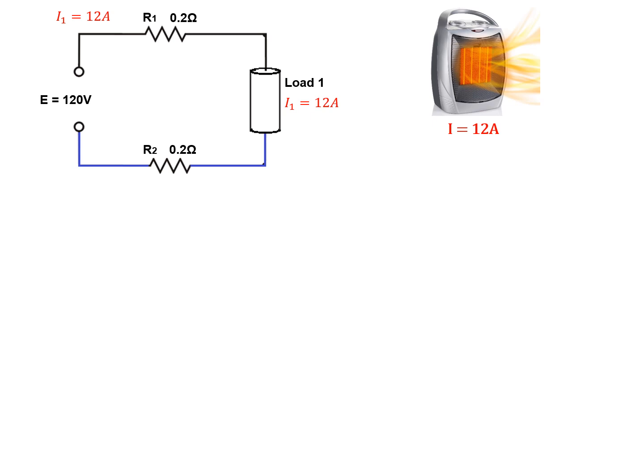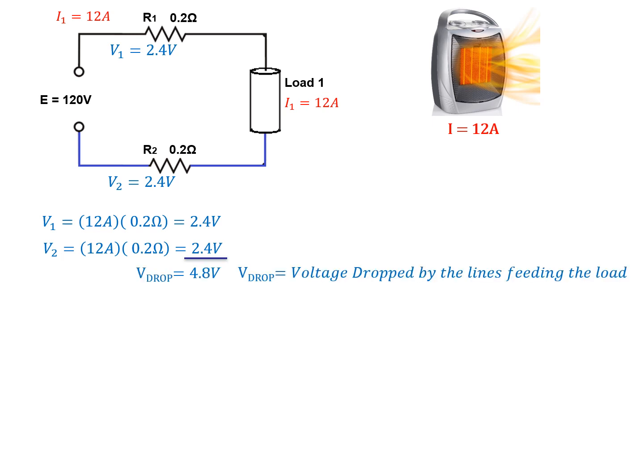Since our load is drawing 12 amps, and our feeder wires, R1 and R2, each have 0.2 ohms, we can calculate the voltage drop for those two lines, where each of them are going to have a 2.4 volt drop. We call this the voltage drop. This is the voltage that is dropped by the lines that are feeding the load. It's a series circuit, so we can now calculate the voltage to the load, where the voltage of the load is equal to our source subtract our voltage drop, which in this case is 120 take away 4.8 volts, for a total of 115.2 volts.